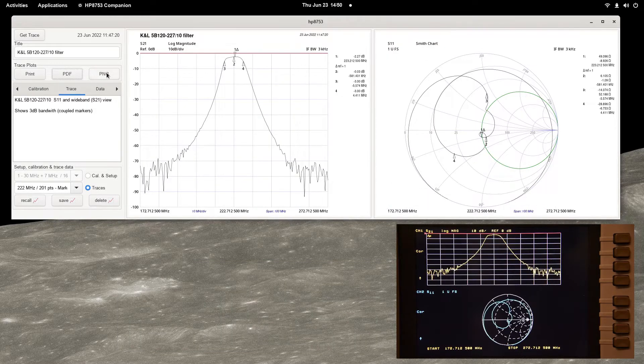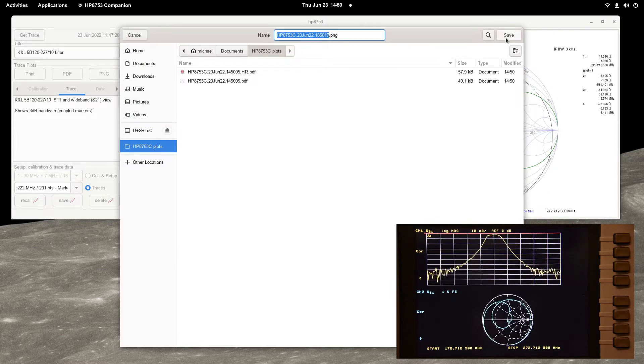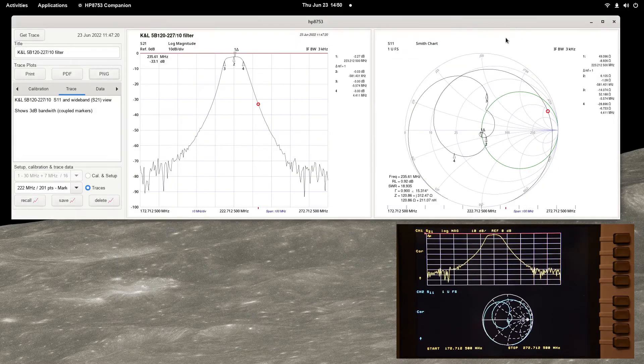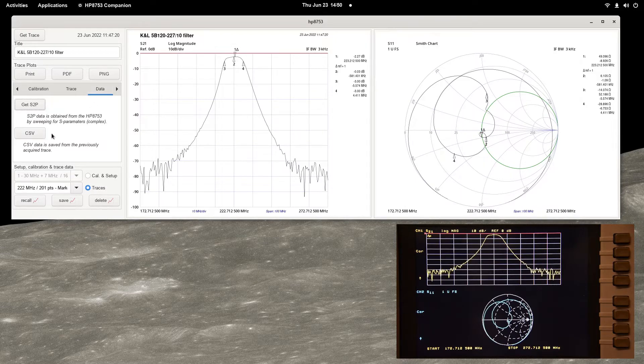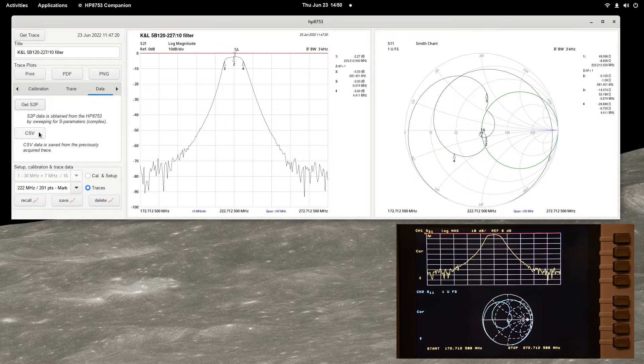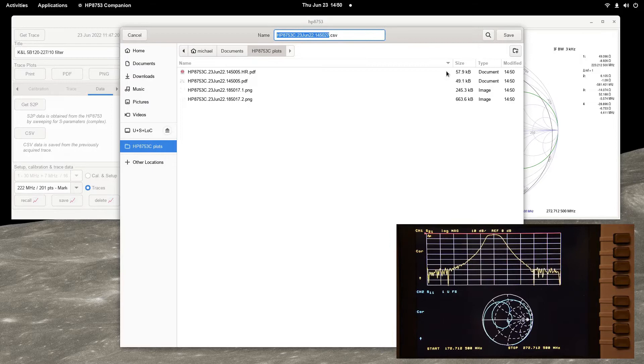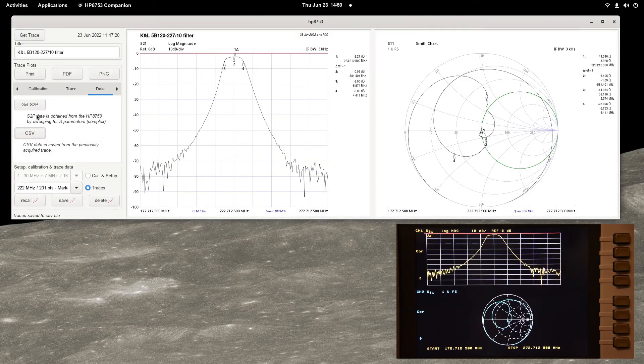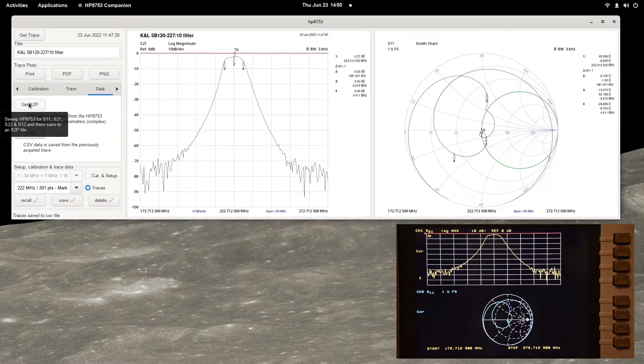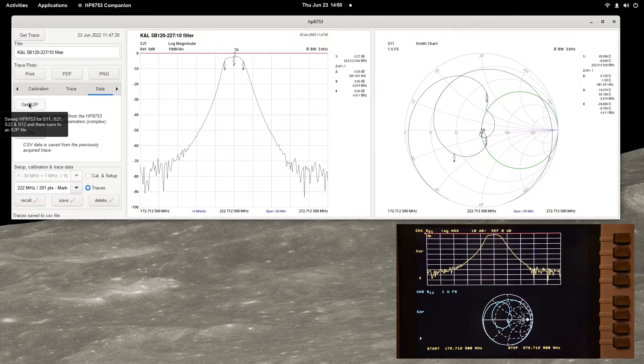CSV data is saved by selecting the data page and then pressing the CSV button. Press the S2P button to instruct the analyzer to take four complex S-parameter measurements and save them in the specified file in touchstone format.